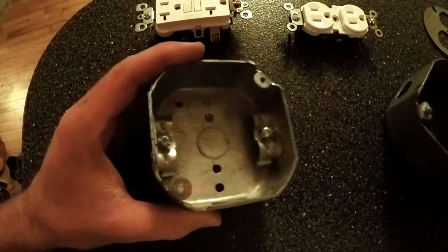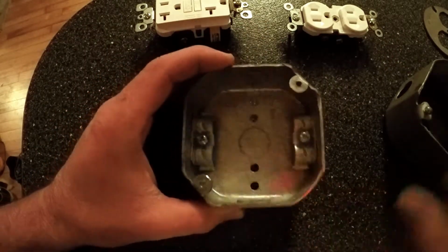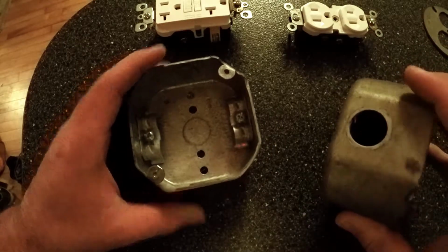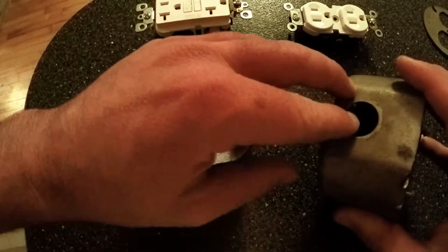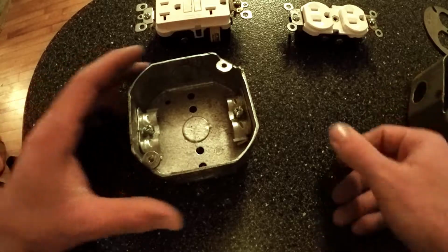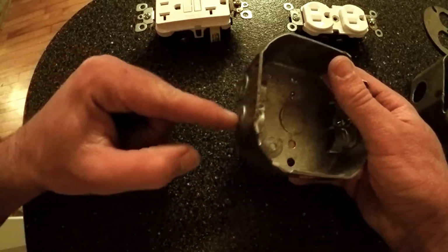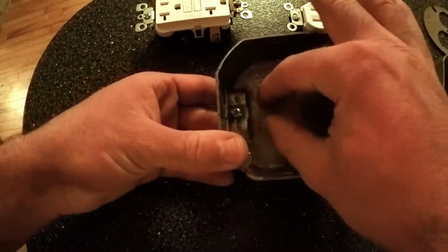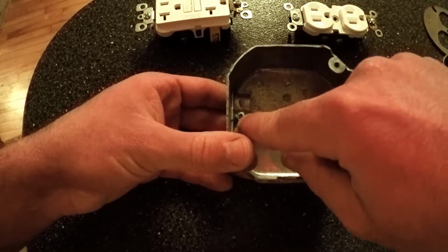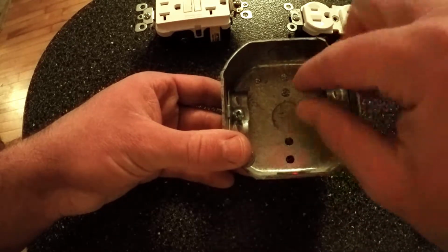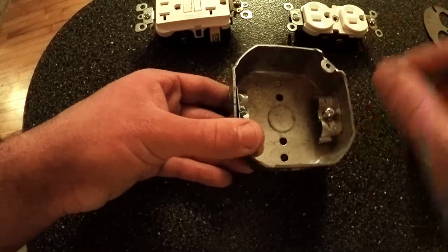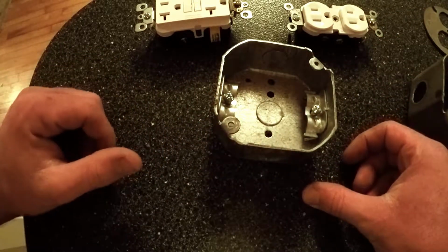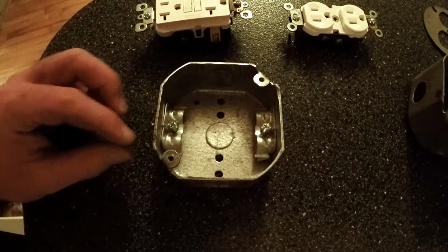These boxes have cable clamps built in. If you have a box without them, you can buy cable clamps separately and put them onto the edge. The cable clamp does exactly what it sounds like: when your lead goes through the hole on the outside, it sits in here, and you have the screw in the center. You tighten that down all the way, and it clamps the cable into place so it doesn't shake loose. Once that lead is through and secured, your outlet itself gets wired.